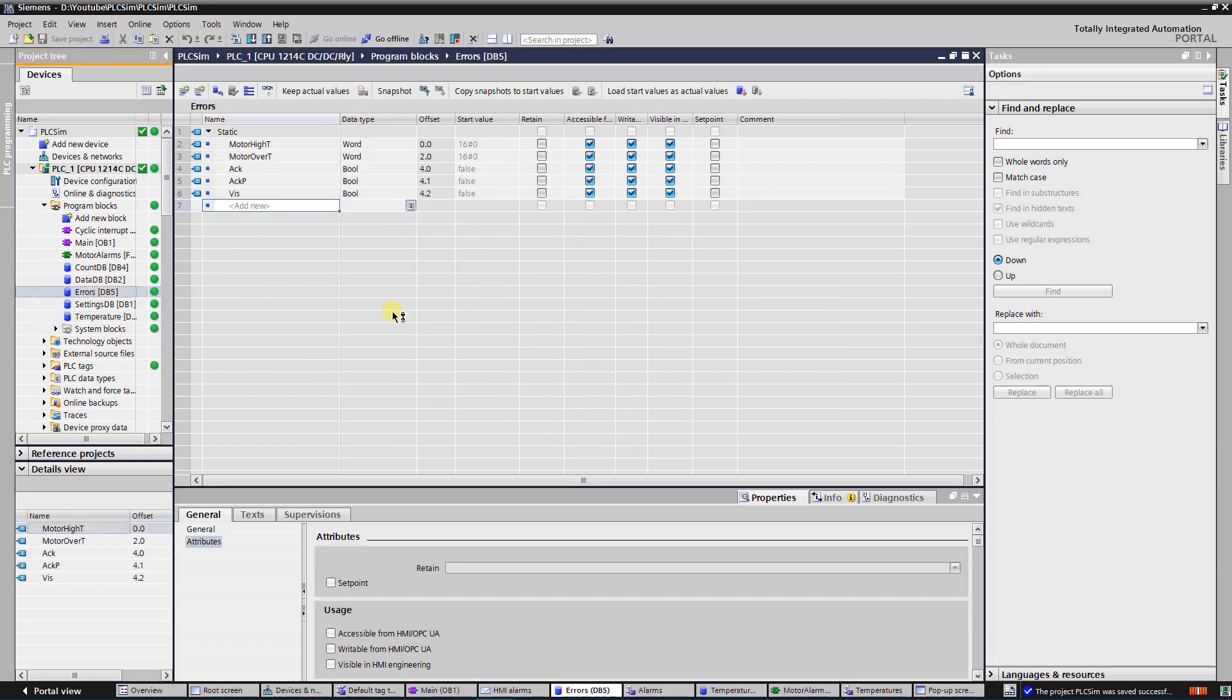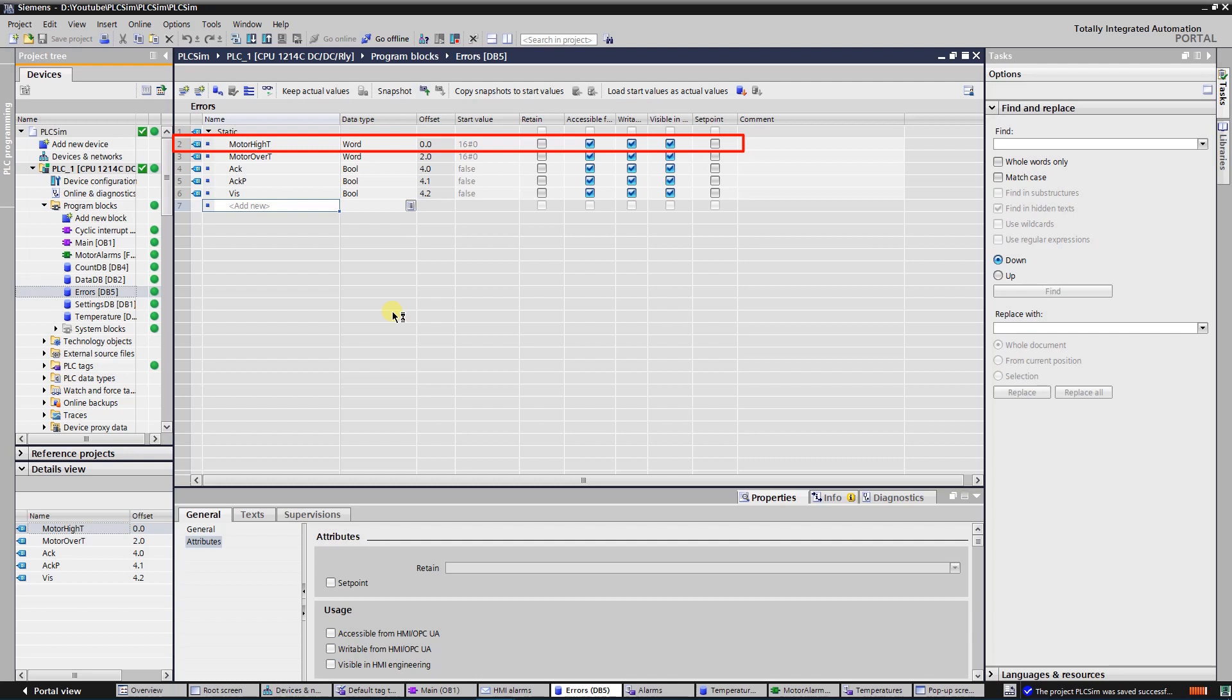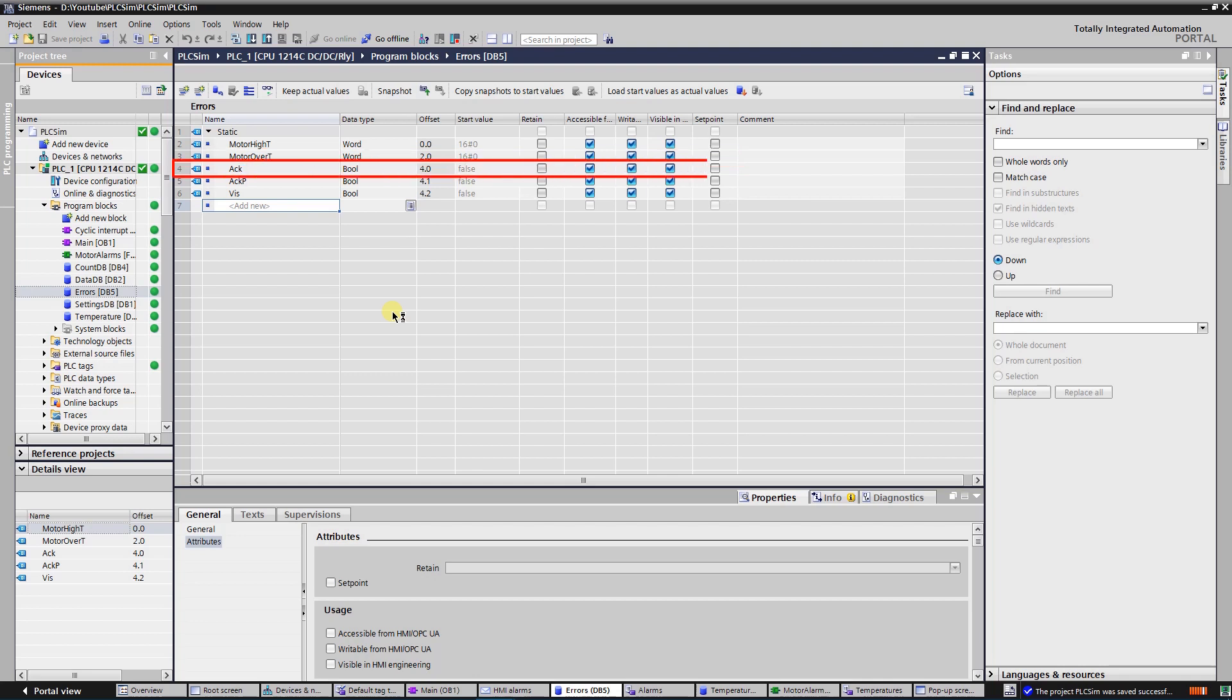Data block number 5 is used to store warning and error bits for operator panel. First word type tag contains warnings of temperature of 16 motors in total. Second word type tag contains errors of temperature of 16 motors in total. To reset errors all at once, a tag named ACK is created.